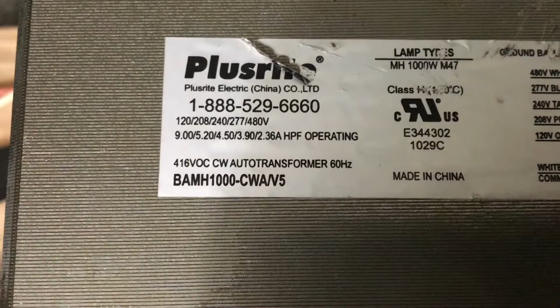The open circuit voltage on this ballast is 416 volts, which is super high—you can get shocked. All the different wires are color coded: 120 volt is orange, 208 is purple, 240 volt is tan, 277 volt is black, and 480 volt is white.